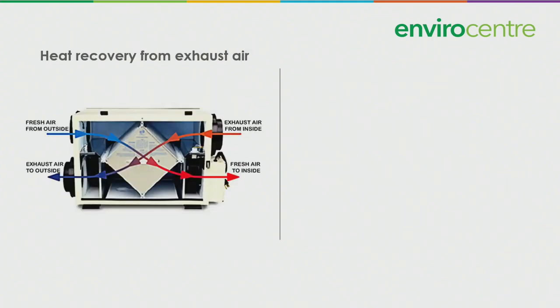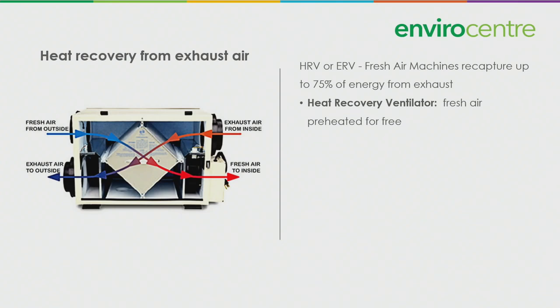Heat recovery from exhaust air. We mentioned this already with the makeup air - you're going to capture up to 75% from the exhaust. With an HRV, heat recovery ventilator, you get your fresh air preheated for free. The ERV will do it and also provide humidity regulation.